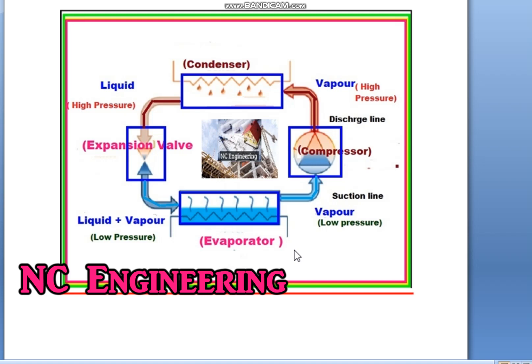Commonly we use refrigerant R22. The boiling point of R22 is minus 40 degrees. So whenever our application temperature is higher than minus 40 degrees — suppose in a room we need cold air at 17 degrees — when this air of higher temperature comes in contact with the coil surface where this refrigerant is flowing, it will give its heat to the refrigerant and the air will become cold.